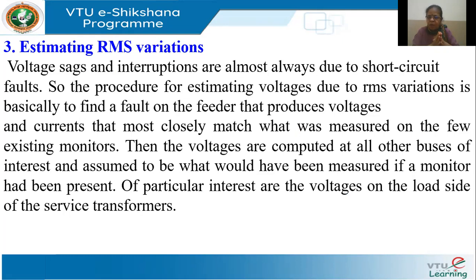So there are standard procedures for that, as I told you. I keep iterating on the estimated values till such time that the estimated value matches the measurement which we have taken. Then I can assume that on all the other buses where I have not measured, the estimated values are accurate. See, what this means is this. Let us say I want 100 variables. So instead of monitoring 100, I am monitoring only 50. Now these 50 voltages are a function of all the 100 voltages. So here Z is 50 measurements, X state variable is 100.